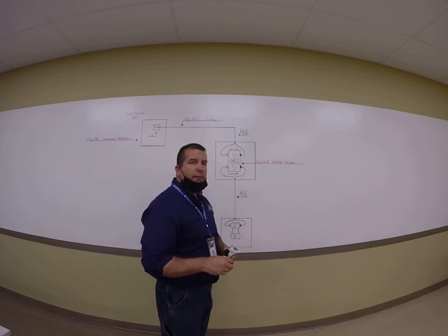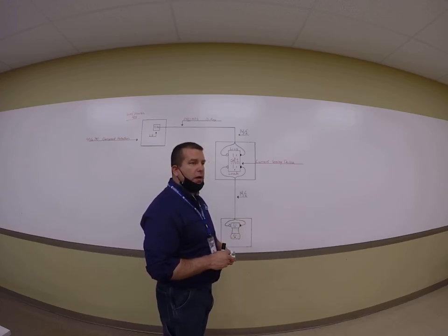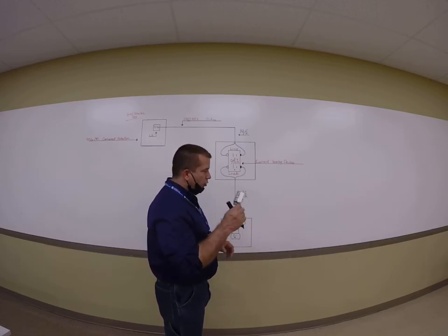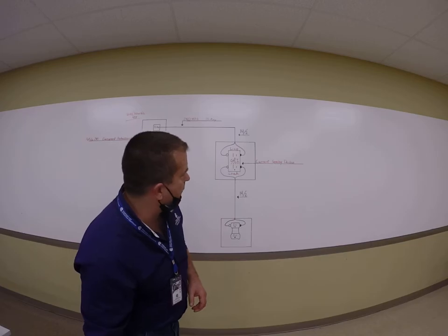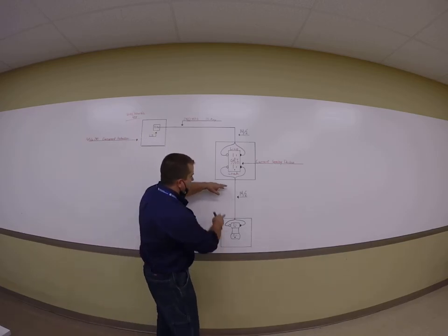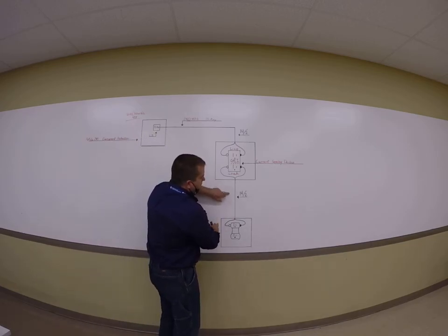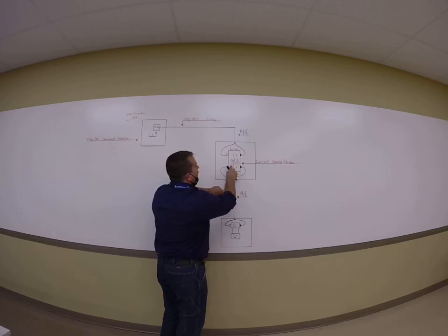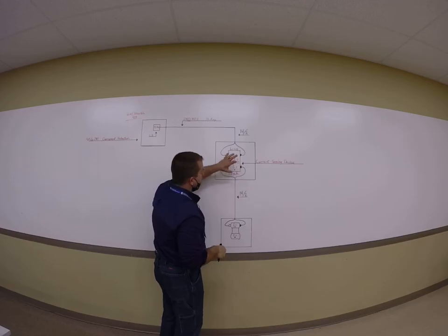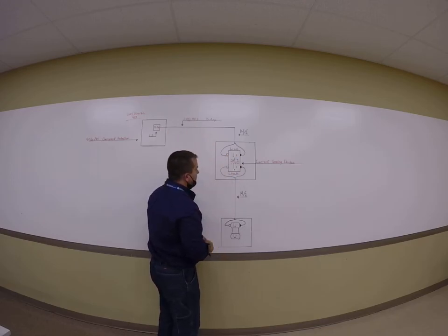And we don't want that, because if it's somewhere else in the circuit, it could be on you if you touch something. So that's the whole purpose of these ground fault circuit interrupters. Anything that's on the load side of the device has to go through this so it can be sensed, so it can trigger if it sees leakage current and then make its way back home.